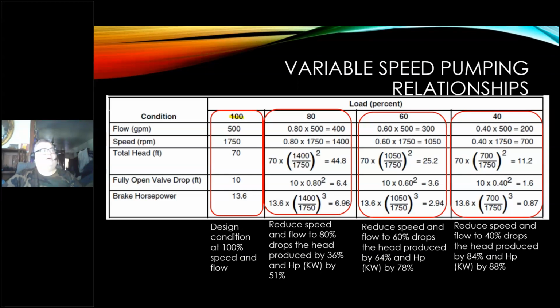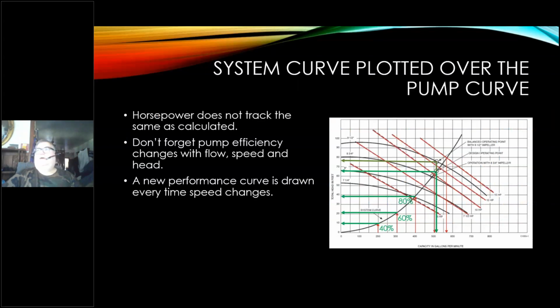And that comes up on some systems. The horsepower does not track the same as calculated. Don't forget the pump efficiency also changes with flow, speed, and head, but we did not calculate that. That's another presentation. We could spend a lot of time just on that. A new performance curve is drawn every time the speed changes.